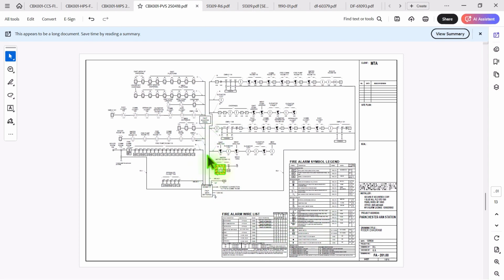The one-line diagram — this is good, so don't think it's not right. This is absolutely right, but only when we're doing New York City fire alarm work to get approval from the fire department, when we're trying to get a system approved — they want a one-line diagram. However, when we're installing the system, we have to show the conduits, the amount of conduits running out of the panel. That's what confused me at first, but now I understand: from an installer's perspective, if we have 4 or 5 circuits, we need to show those circuits and whatever they're actually serving. So that's all we have to do — I'll show you what that is in a second.